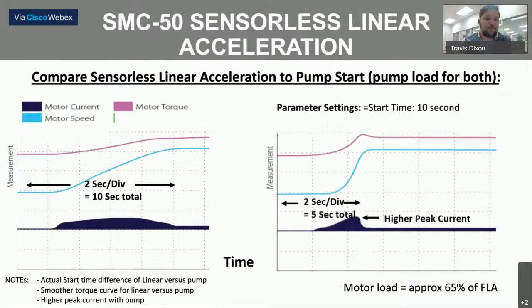This is an example of the linear acceleration versus a pump start. Sensorless acceleration, like I said, is that patented unique feature. There's no external feedback needed with this. It provides exact motor acceleration control under varying load conditions, much like a drive. There are only 2 parameters to configure: you use a minimum amount of energy needed to accelerate the motor, and the time requested.